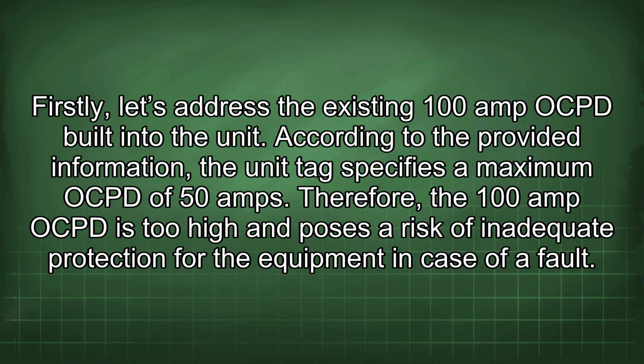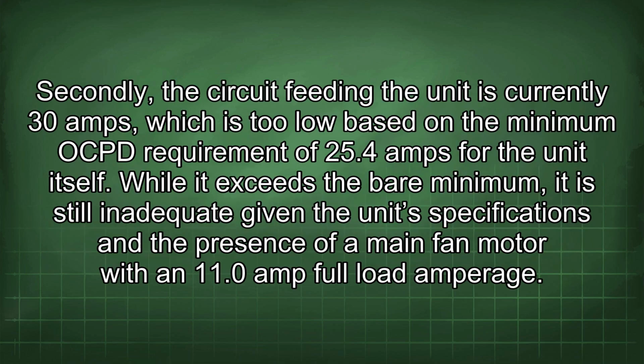of a fault. Secondly, the circuit feeding the unit is currently 30 amps, which is too low based on the minimum OCPD requirement of 25.4 amps for the unit itself. While it exceeds the bare minimum, it is still inadequate given the unit specifications and the presence of a main fan motor with an 11.0 amp full load amperage.